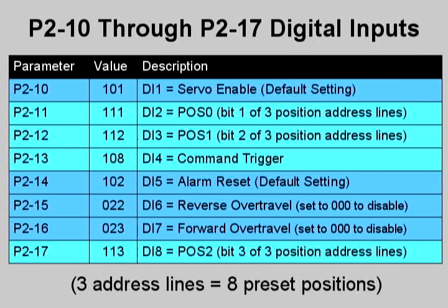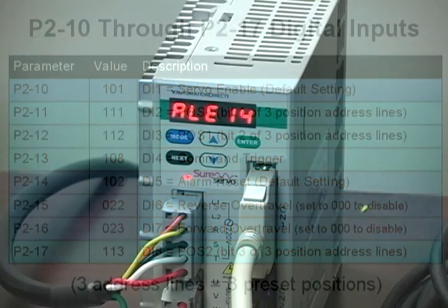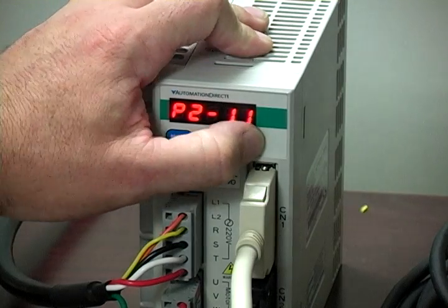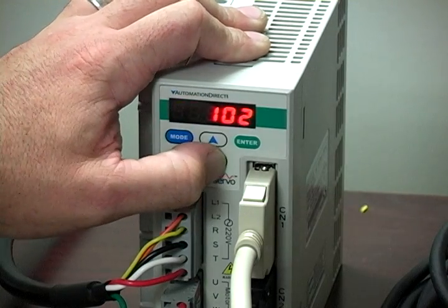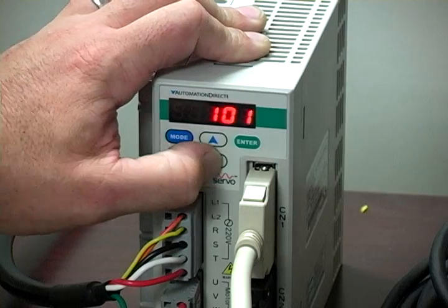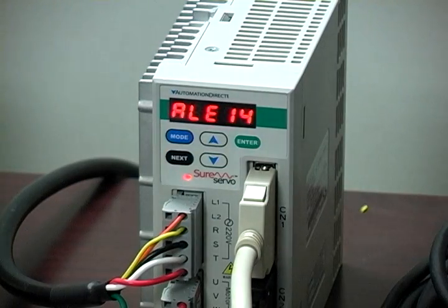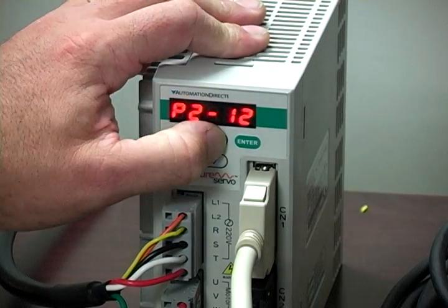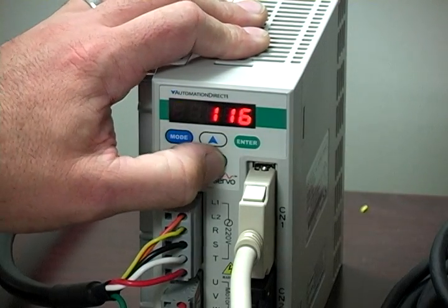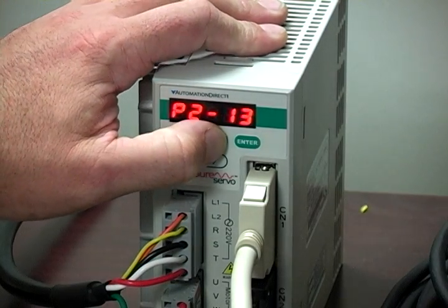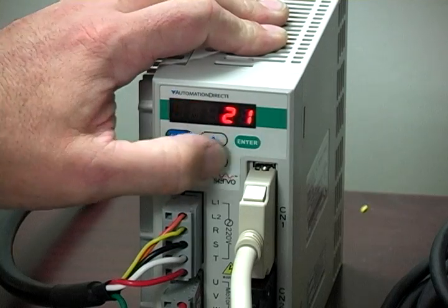We have wired our push buttons to inputs 2, 3, and 8, so we will need to set up those inputs internally in the drive. To configure digital input 2 as POS0, P211 will be set to 111. To configure digital input 3 as POS1, P212 will be set to 112. And to configure digital input 8 as POS2, P217 will be set to 113.